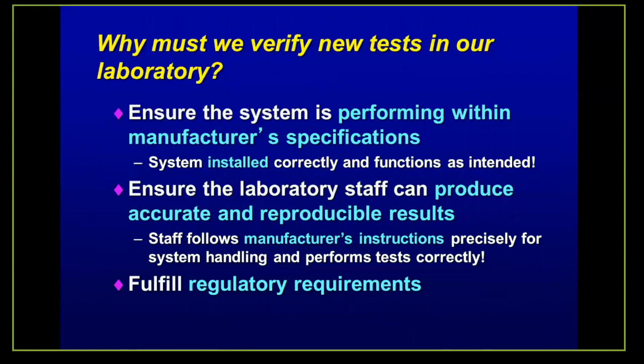Why do we have to verify our new tests in our laboratory? We need to do this to make sure that our system is performing within the manufacturer's specifications. We need to make sure that the system was installed correctly and it is functioning as it is intended.